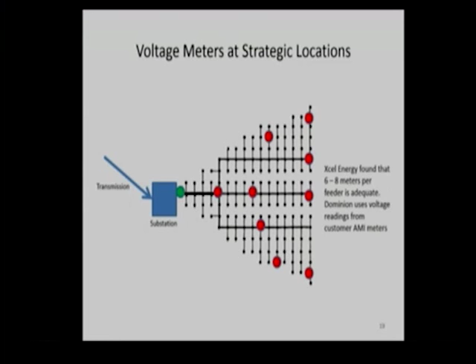This requires us to really put voltage meters at strategic locations in the grid. Xcel Energy has done some pilots, and I'll show you a slide on that in a minute, but they found they really only needed 6 to 8 meters for each feeder. If you have AMI meters at customer locations, you can use those, but you don't have to have them. You can put standard meters on key locations within the grid, and you don't really need that many of them.